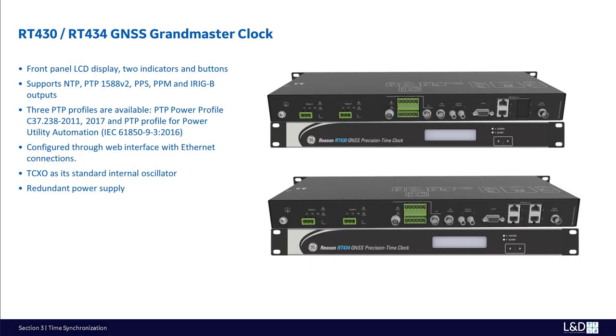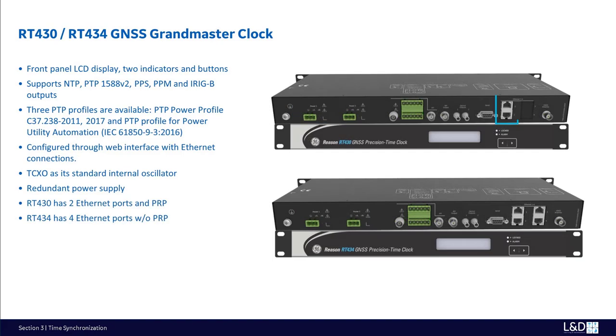RT430 and RT434 have an optional second redundant power supply with AC-DC high voltage or DC low voltage options. The RT430 has 2 Ethernet ports and optional PRP functions, while the RT434 has 4 Ethernet ports without PRP function. Choose the RT430 in Ethernet applications where IEC 62439 PRP redundant architecture is required. Choose the RT434 where 3 or 4 electrical network ports are required.